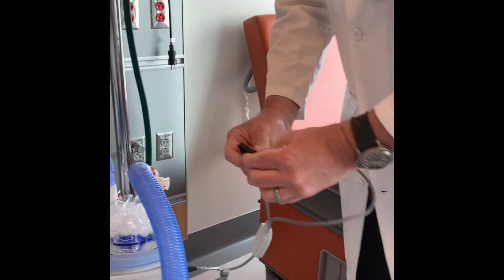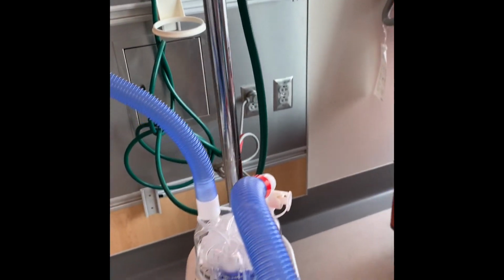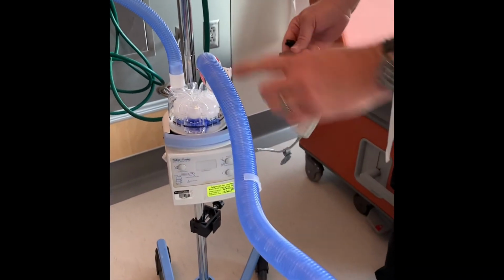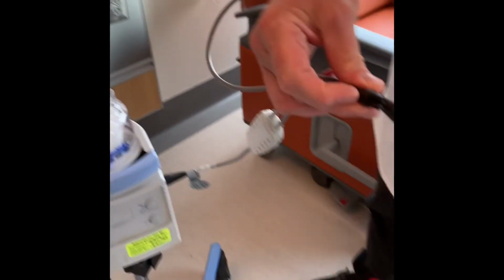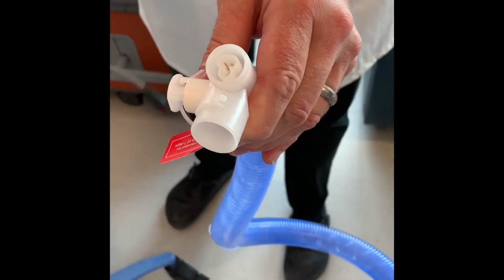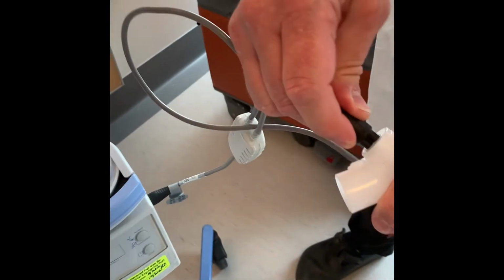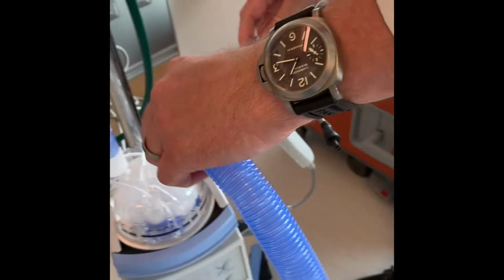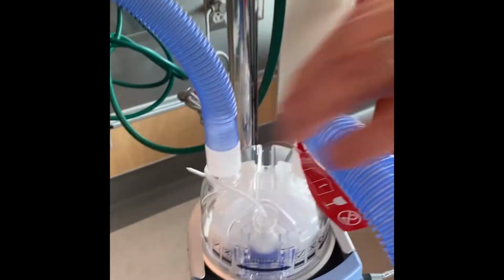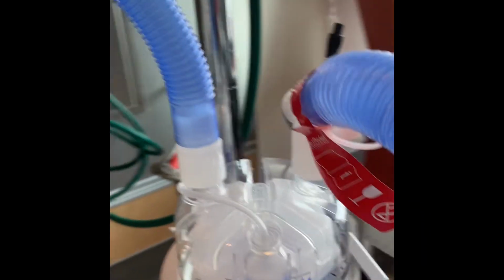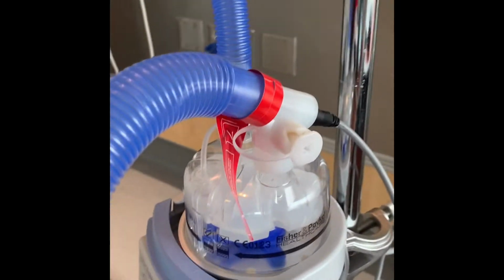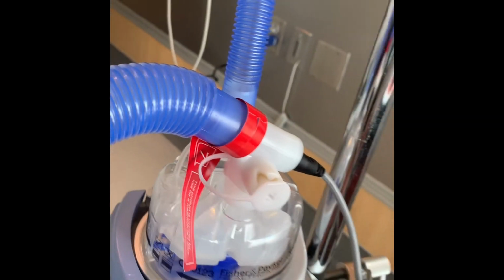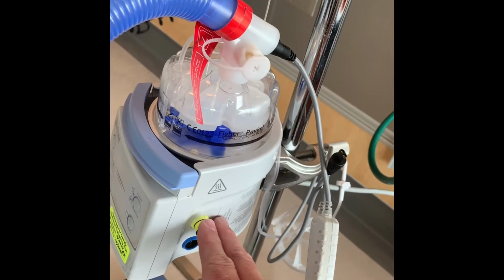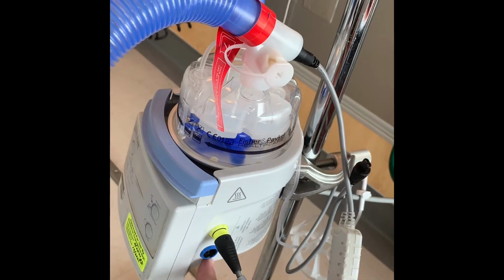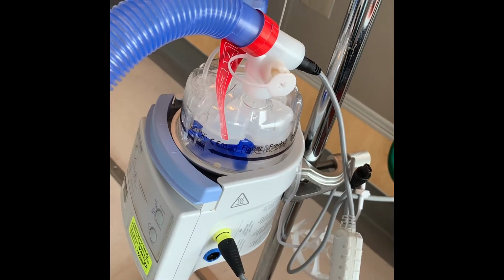And on the pigtail, all it does is heat this wire inside of this corrugated tubing. You'll see that there's a port in the back, and the pigtail just fits right into the port. So that will heat it. The last piece of the puzzle is we have to put a temperature probe, which needs to be cleaned. So this is always on the machine, but the temperature probe is not always on the machine because it gets cleaned by CSPD in between uses.